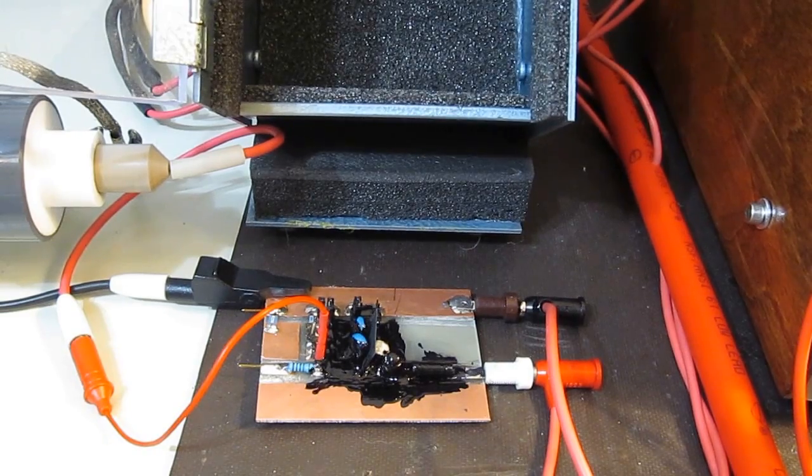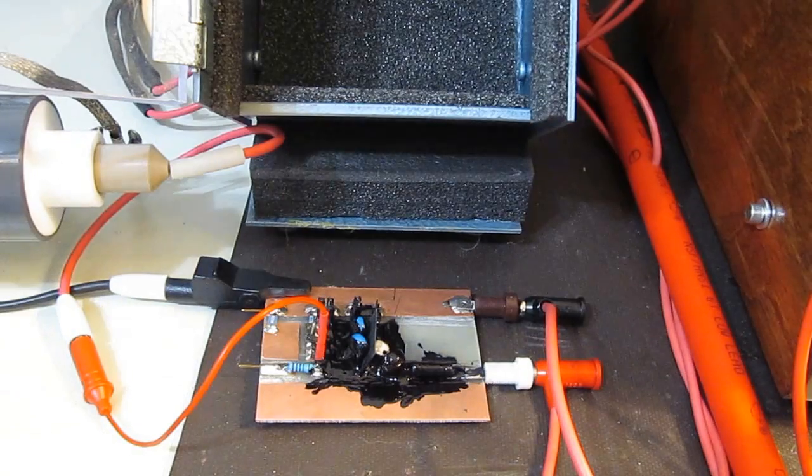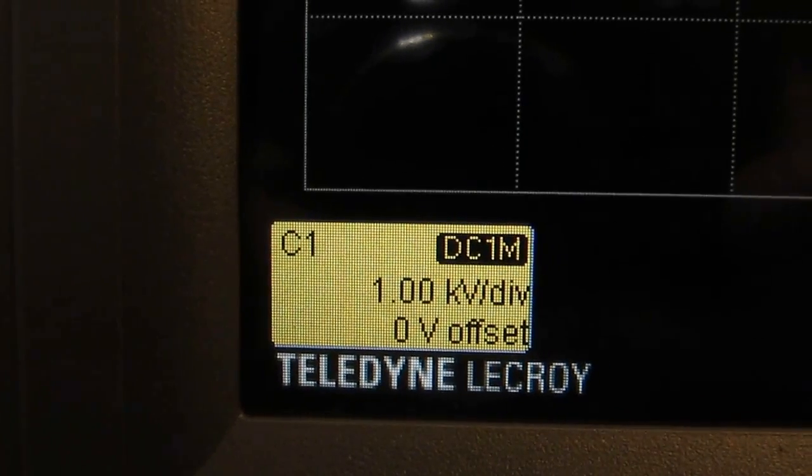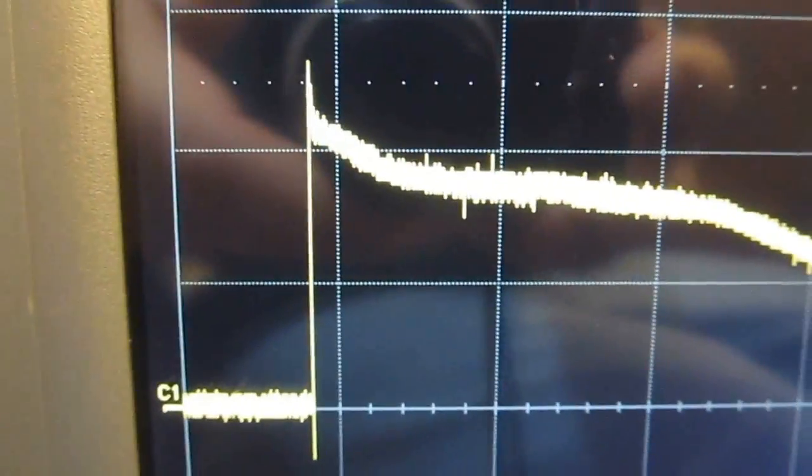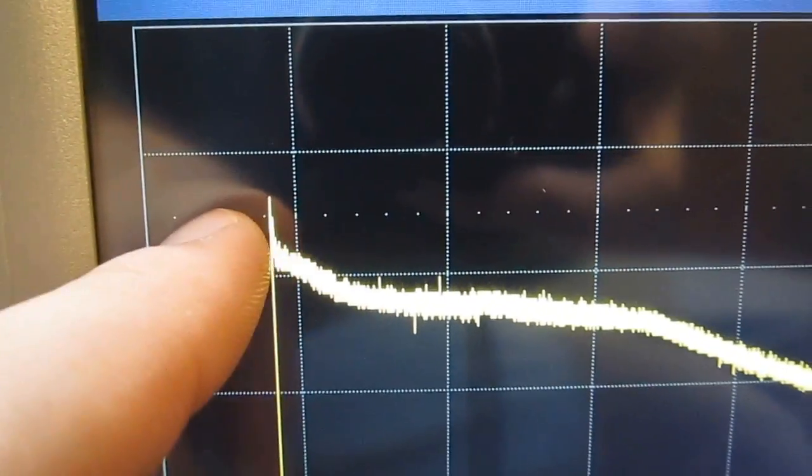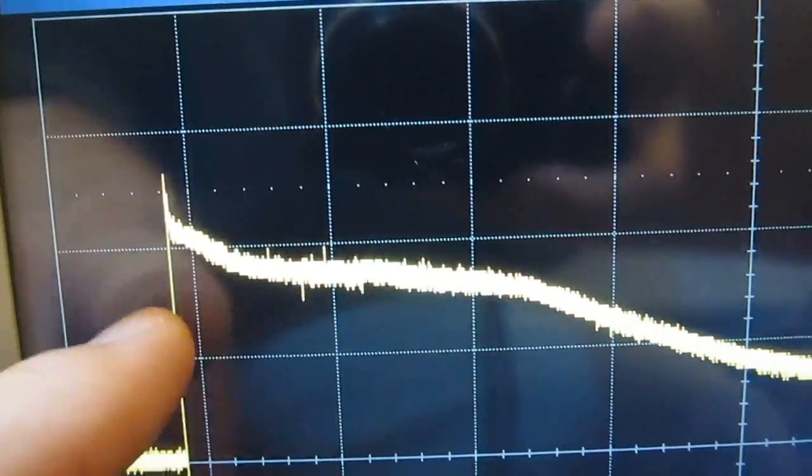Okay. We'll give it a single transient. The LeCroy is currently set for 1,000 volts per division and 50 microseconds per division. As you can see here it's clamping at roughly 2.6 kilovolts. And then it settles down pretty quick.